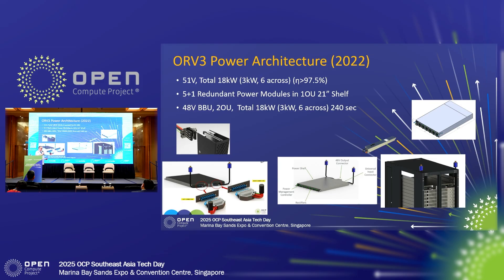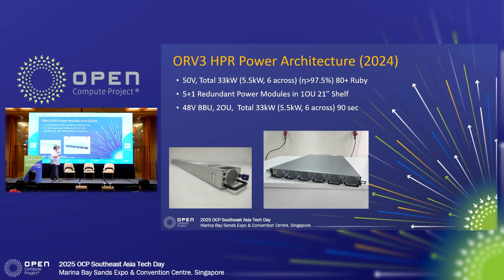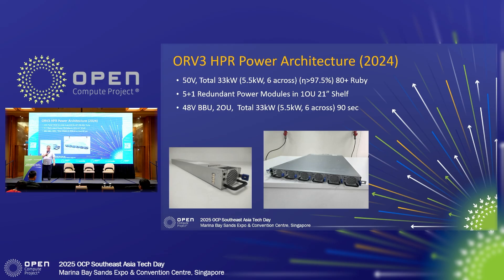That's ORV3, which was the standard until just recently when AI came along and said 15 kilowatts plus one is not enough — I need 30 kilowatts, 60 kilowatts. The GB200 needs 120 kilowatts in a rack. So we needed something new: ORV3 HPR. We went from 3 kilowatts per power supply to 5.5 kilowatts per power supply, so that shelf now has 33 kilowatts in it.